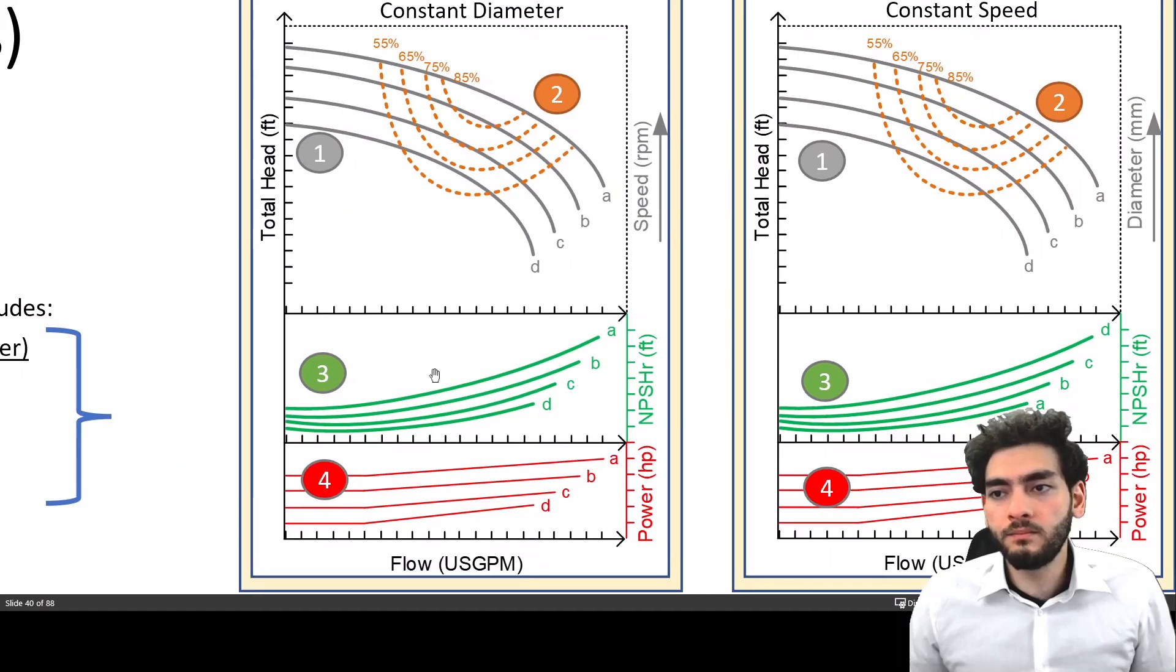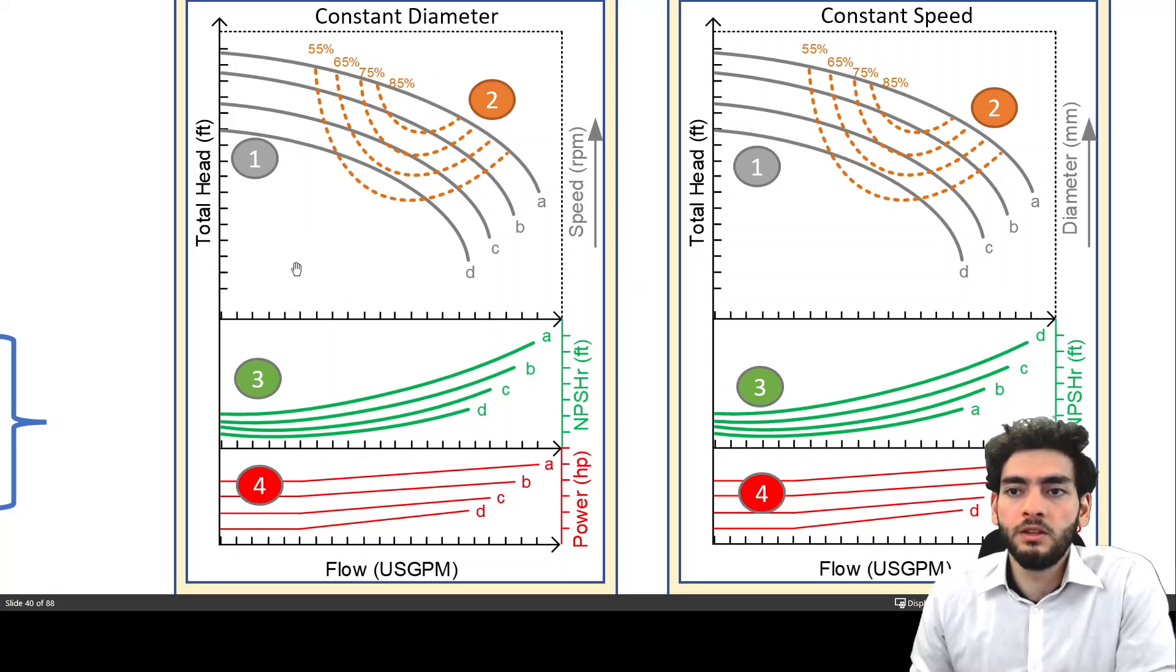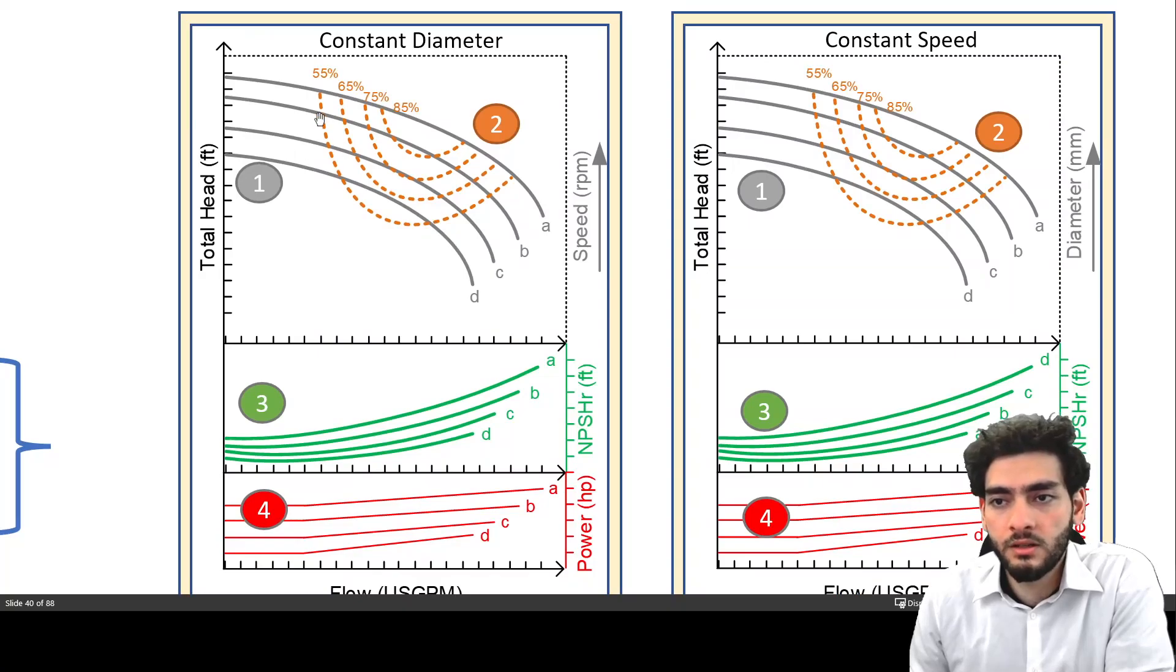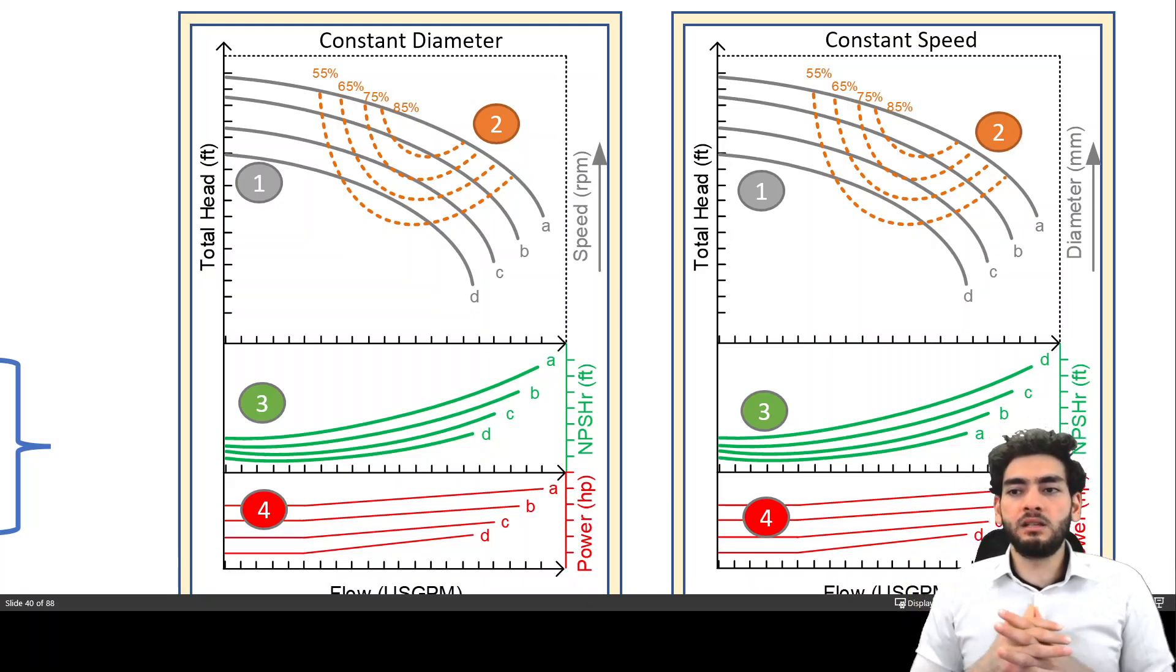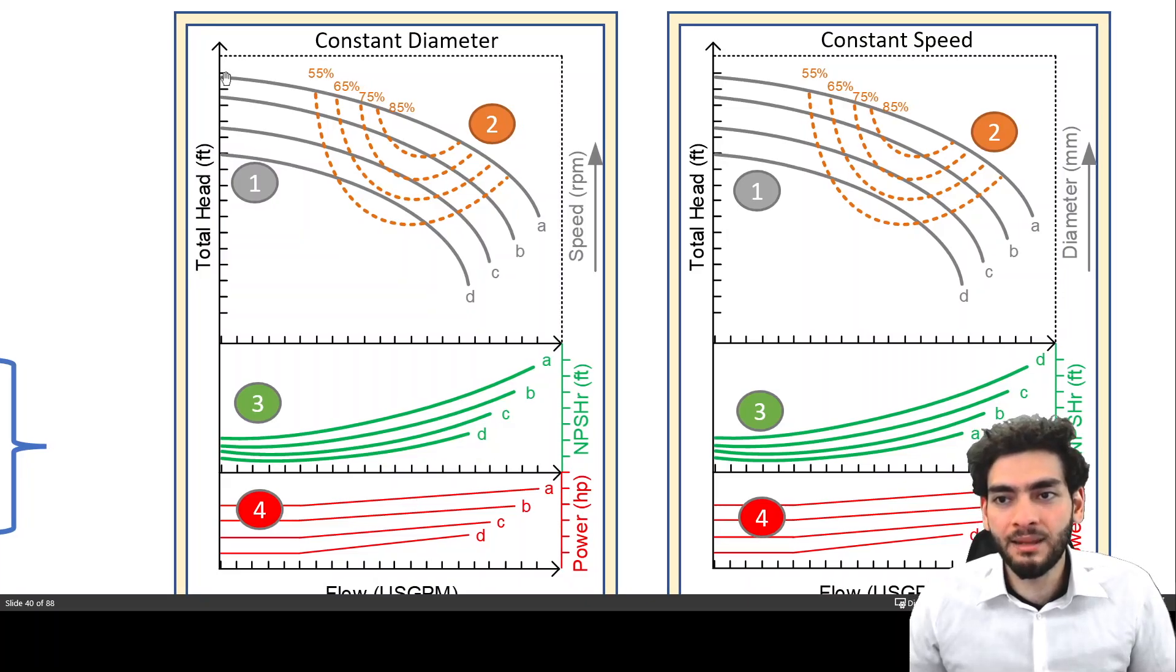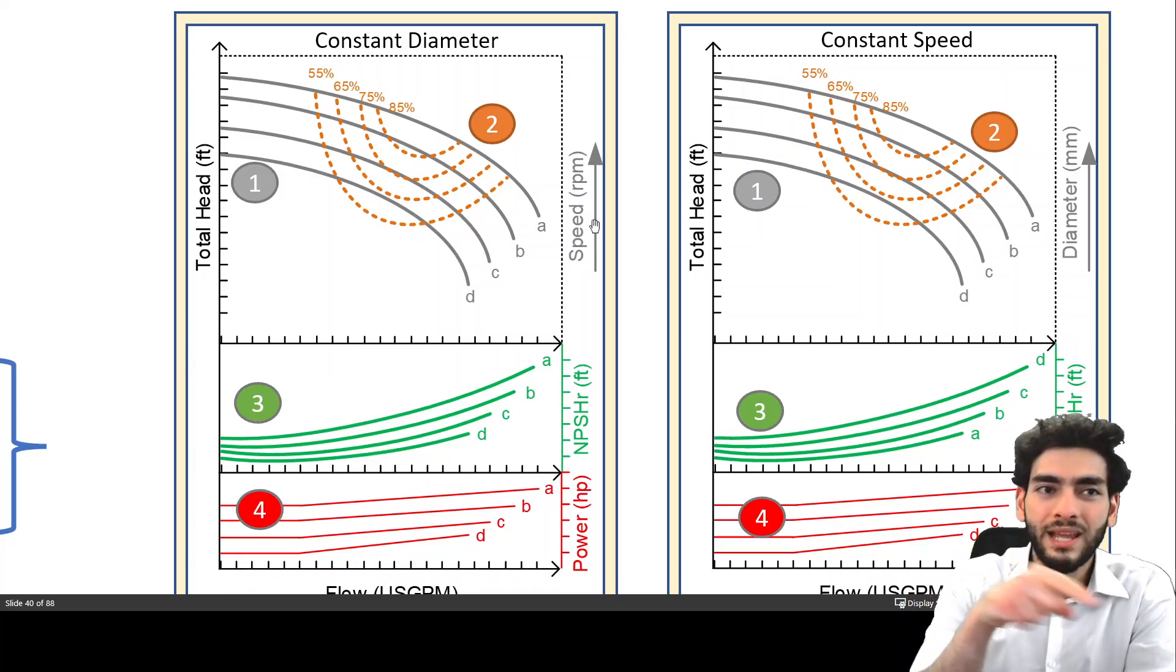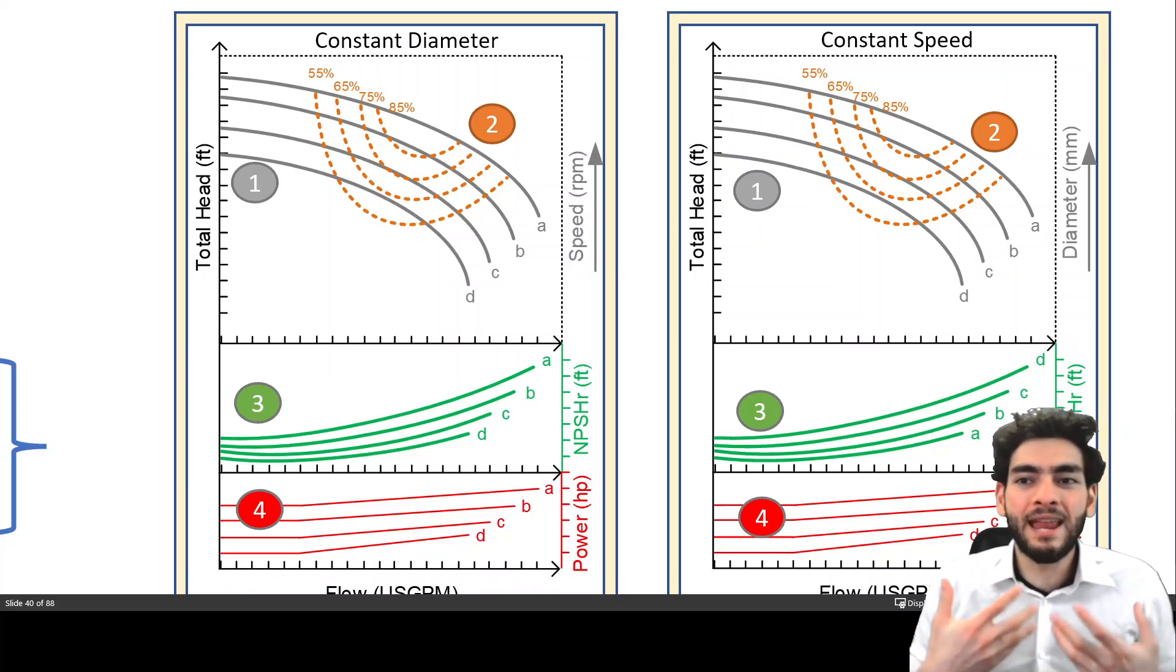So if we look at what essentially the curves look like, for a constant diameter, you can have multiple head curves depending on what speed the impellers will rotate at. And that is something that you could decide if you have a VFD, which is a variable frequency drive installed at your pump. So you could see, we've discussed that the pump curve essentially looks like this for a centrifugal pump. And if you increase the RPM, which is the rotation of the impeller, you could basically shift the curve upwards so you could generate more flow rate and more head.